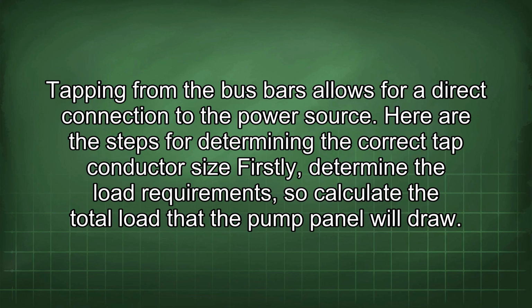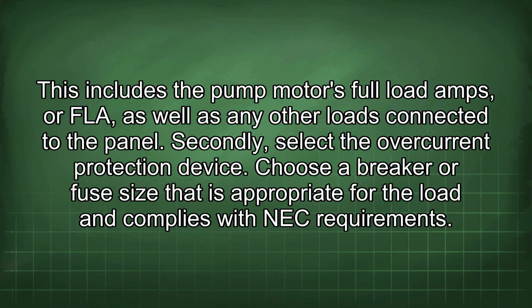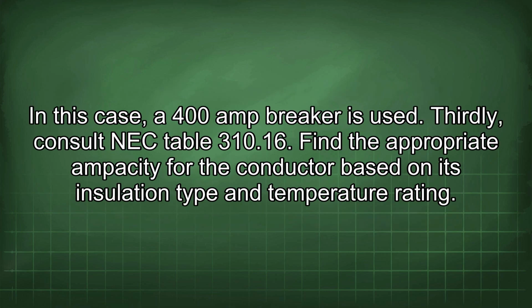Here are the steps for determining the correct tap conductor size. Firstly, determine the load requirements, so calculate the total load that the pump panel will draw. This includes the pump motor's full load amps, or FLA, as well as any other loads connected to the panel. Secondly, select the overcurrent protection device. Choose a breaker or fuse size that is appropriate for the load and complies with NEC requirements. In this case, a 400 amp breaker is used.